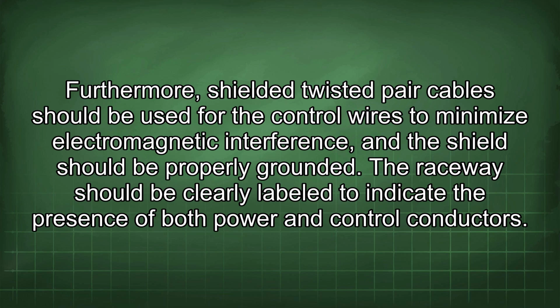Furthermore, shielded twisted pair cable should be used for the control wires to minimize electromagnetic interference, and the shield should be properly grounded. The raceway should be clearly labeled to indicate the presence of both power and control conductors.